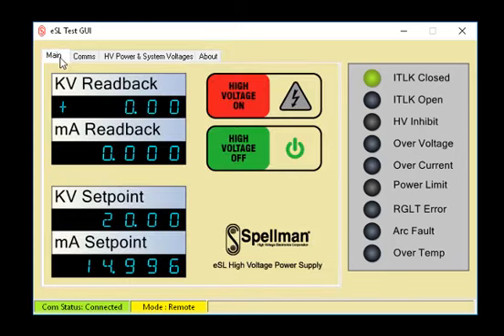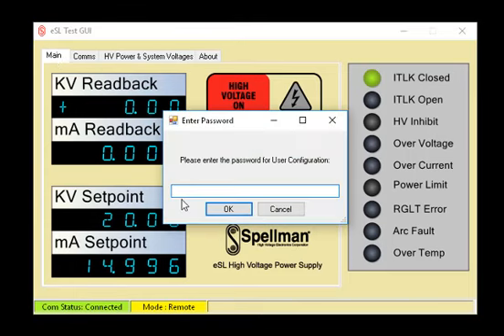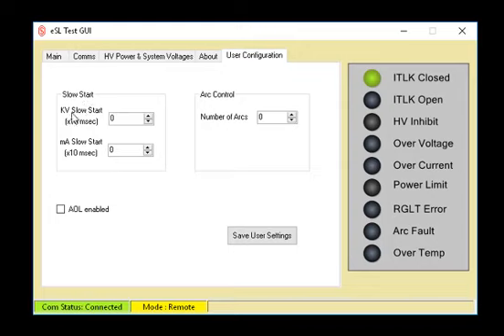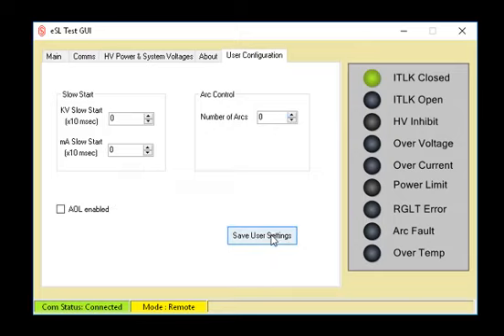Let's go back to the main tab. The eSL manual explains how to access the user configuration tab. Let's open this tab. Here you can set KV and MA slow start times. This box allows the AOL option to be enabled. Here you can set the number of arcs for the arc intervention circuitry. Click save user settings to save any changes made.